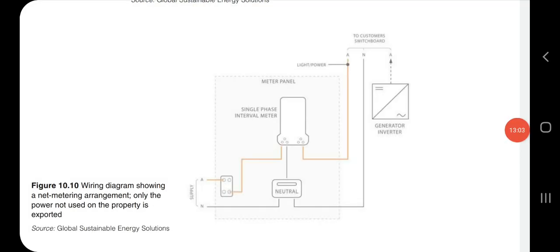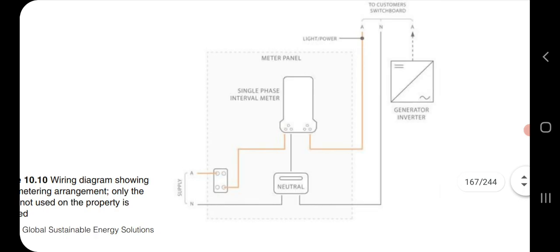Now this is the main wiring diagram shown in the net metering arrangement, how directly from the inverter it goes to the meter. This is the way they have done this wiring. It is very important. For net metering it is different, and for gross metering also it is different.